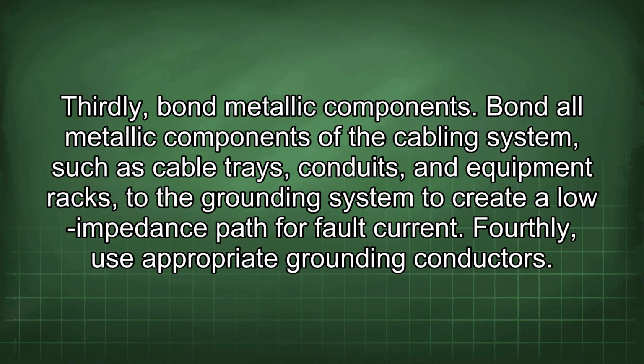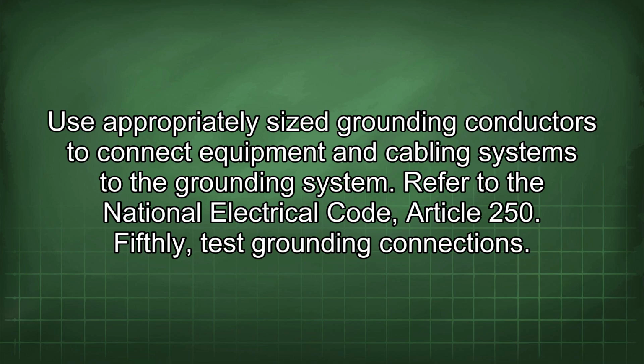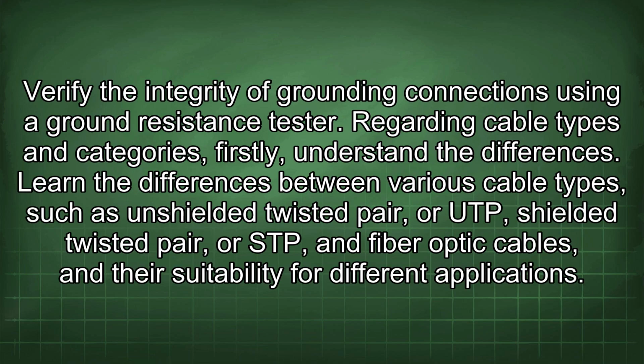Fourthly, use appropriate grounding conductors. Use appropriately sized grounding conductors to connect equipment and cabling systems to the grounding system. Refer to the National Electrical Code, Article 250. Fifthly, test grounding connections. Verify the integrity of grounding connections using a ground resistance tester.